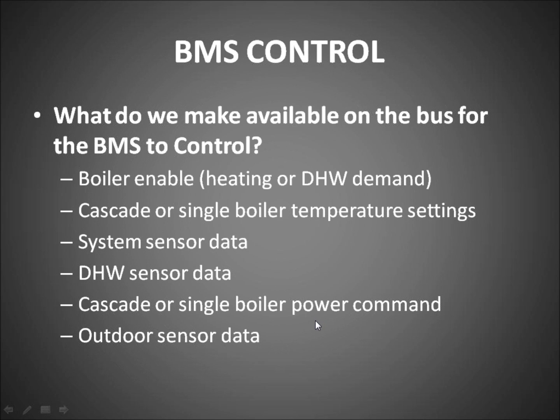BMS control, what do we make available on the bus for the BMS to control? Boiler enabled, so in other words, we can turn the boiler on, heating or DHW demand, cascade or single boiler temperature settings, system sensor data, DHW sensor data, cascade or single boiler power command, so we can command the power, what our modulating rate would be to the fan on the boilers. Outdoor sensor data can also be controlled.